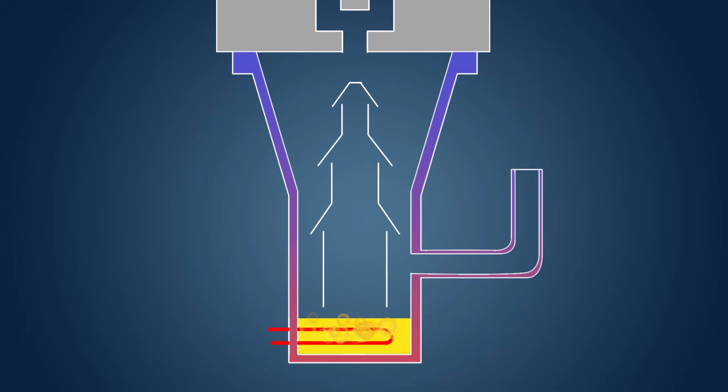Basically, the oil is heated at the bottom and the vapor is sent up through a column of inverted cone-shaped pipes. The vapor is forced through gaps between the pipes in a downward direction and then hits the cooled wall of the pump. This makes it condense and fall back into the boiler. As this happens, the refluxing oil drags any molecules of gas that happen to be floating by down to the bottom part of the pump, where it's redirected out to the mechanical pump to be removed.